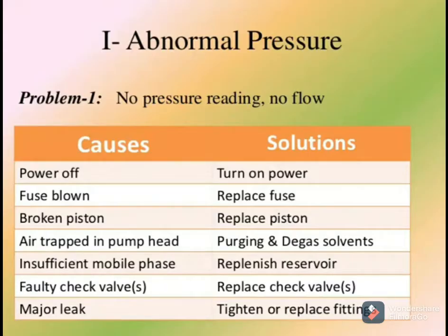Now I will tell you about abnormal pressure. Problem one: no pressure reading and no flow. What is the cause? Maybe the power is off, so turn on the power. If a fuse is blown, replace the fuse. Broken piston, replace the broken piston. Air trapped in the pump head, purge and degas the solvent. Insufficient mobile phase, replenish the reservoir. Faulty check valves, replace the check valves. Major leak, tighten or replace the fitting. These are the causes and solutions.